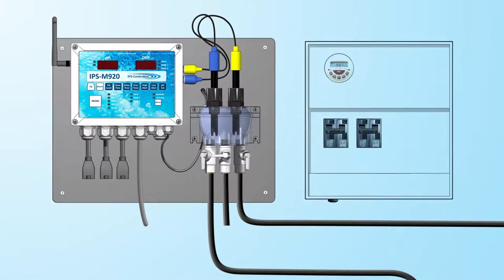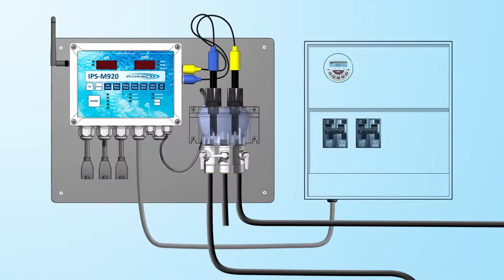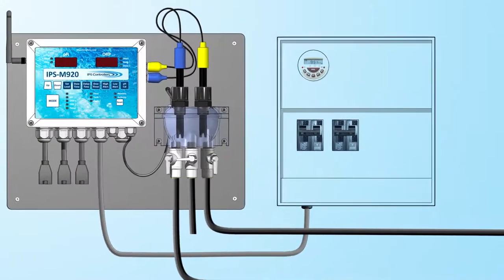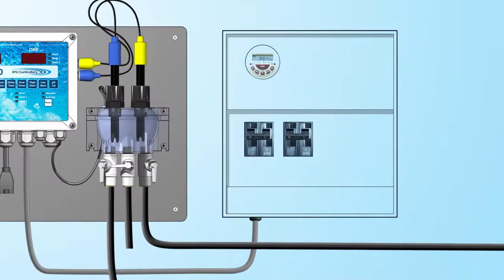To power the unit, the recommended method is to have a professional electrician wire the unit into the time clock on the load side of the circulation pump circuit. This will allow the unit to be turned on only when the system turns on.